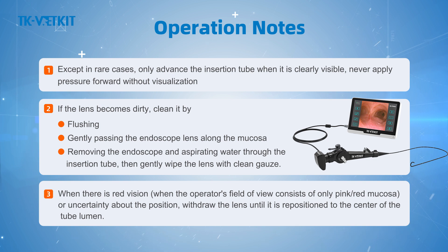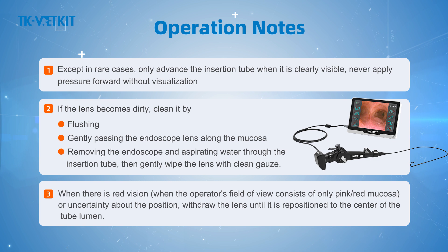Operation notes: First, except in rare cases, only advance the insertion tube when it is clearly visible — never apply pressure forward without visualization. Second, if the lens becomes dirty, clean it by flushing gently, passing the endoscope lens along the mucosa, removing the endoscope, aspirating water through the insertion tube, then gently wiping the lens with clean gauze. When there is red vision — where the field of view consists only of pink or red mucosa — withdraw the lens until it is repositioned to the center of the tube lumen.